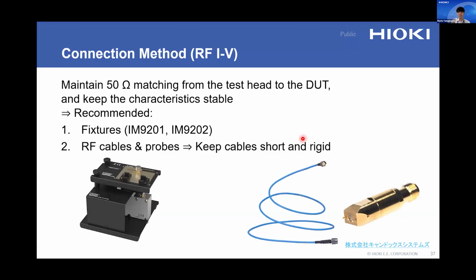Okay, so as mentioned earlier, the key point in RF I-V is to maintain the 50 ohm impedance matching from the test head to the DUT and keep the transmission path stable. For this reason, using a fixture designed for high frequency measurement provides the best accuracy. So if you need to extend the connection, RF cables and probes can be used. However, the cable variation affects the measurement. So cables should be kept as short and rigid as possible.